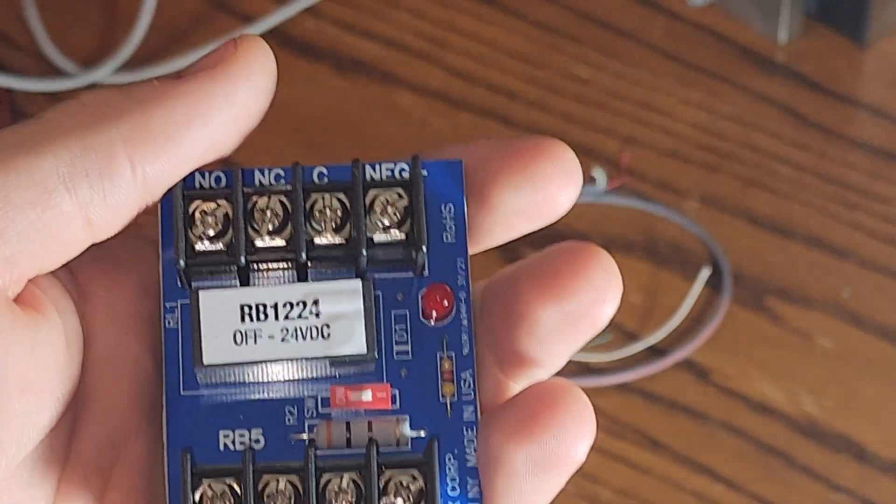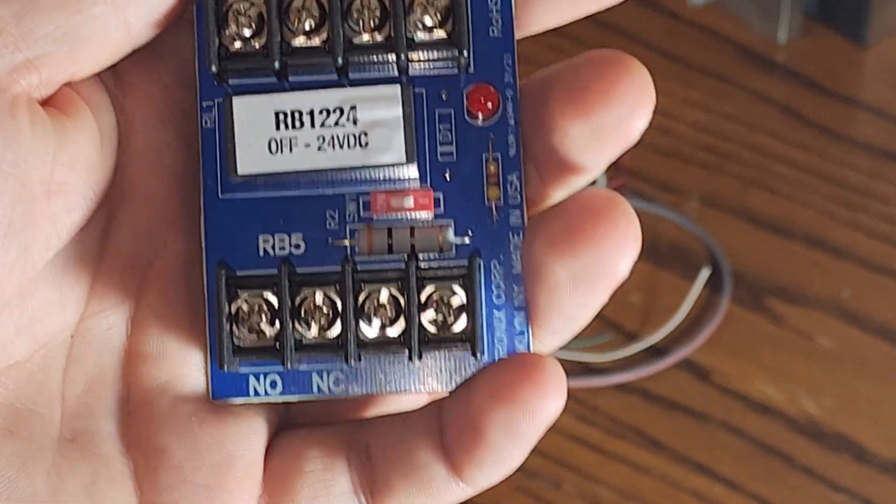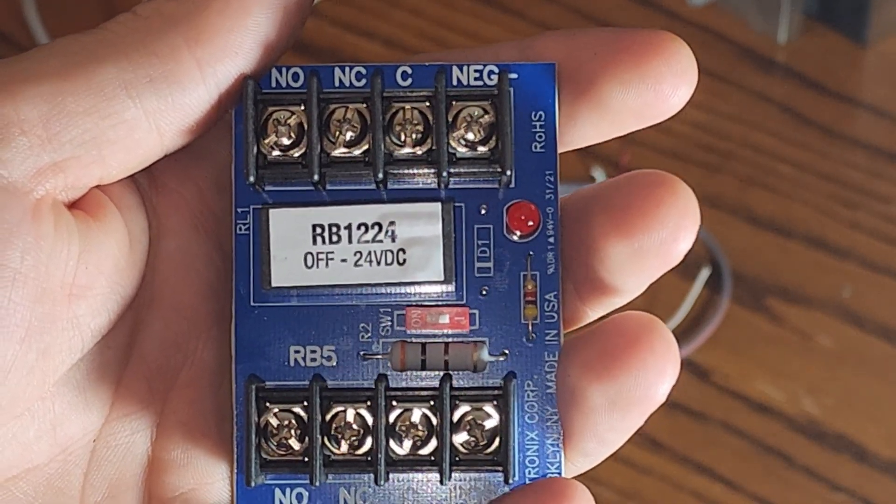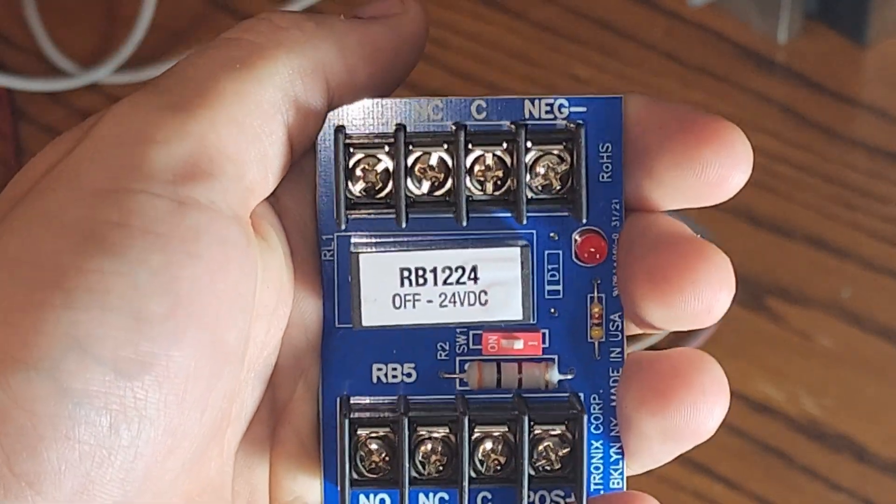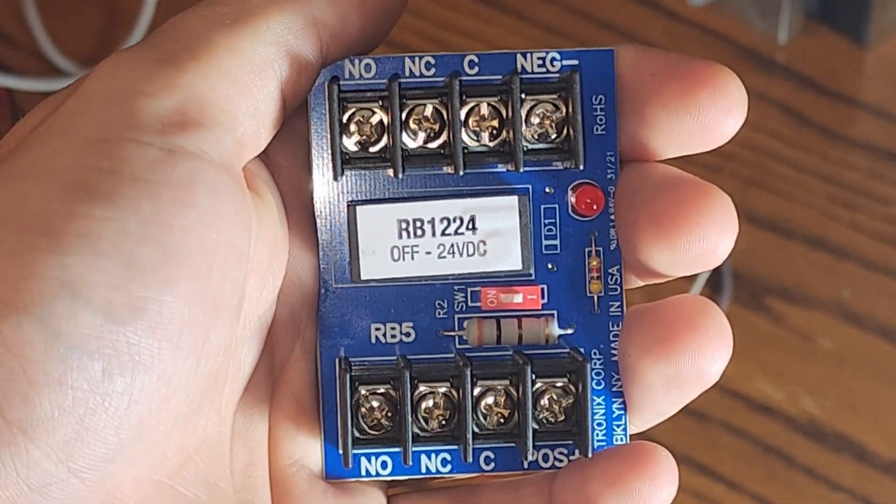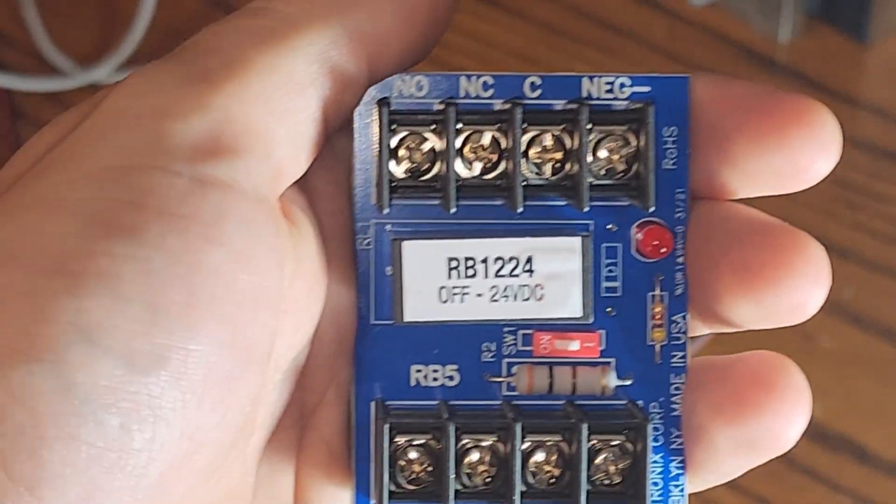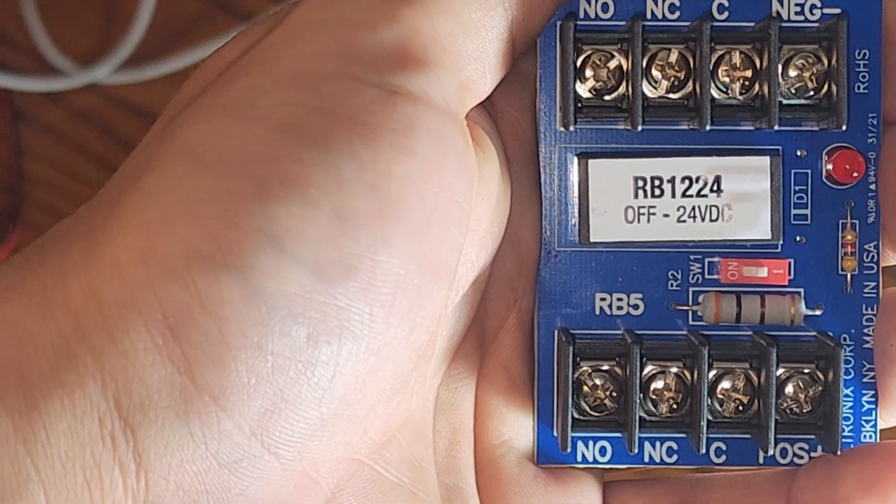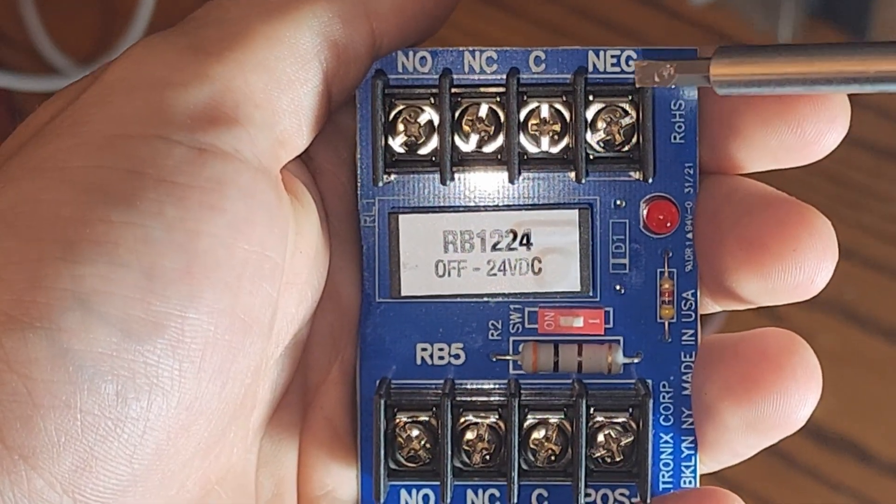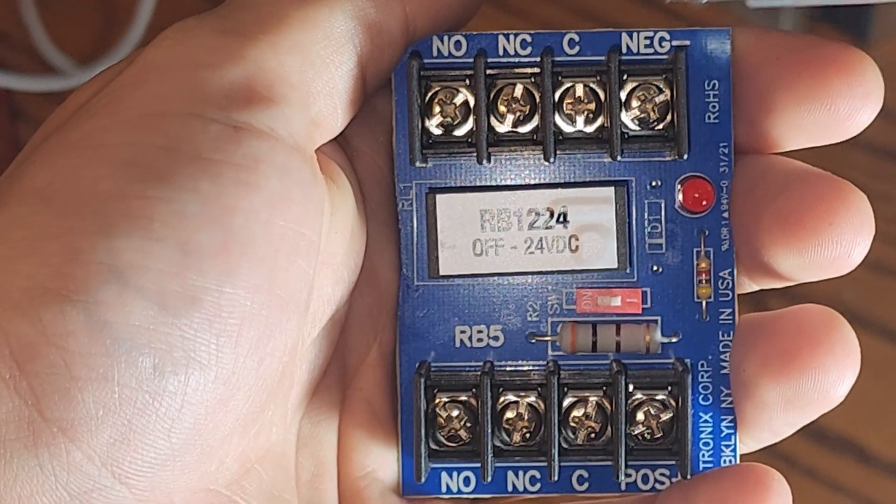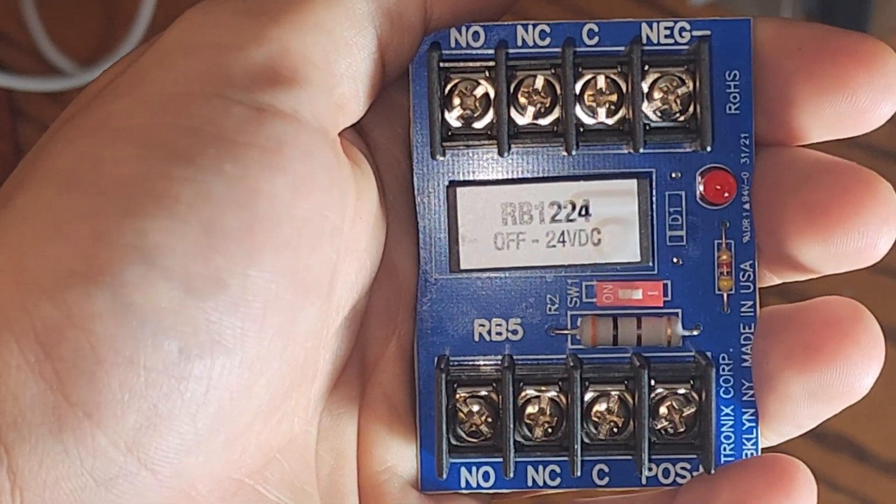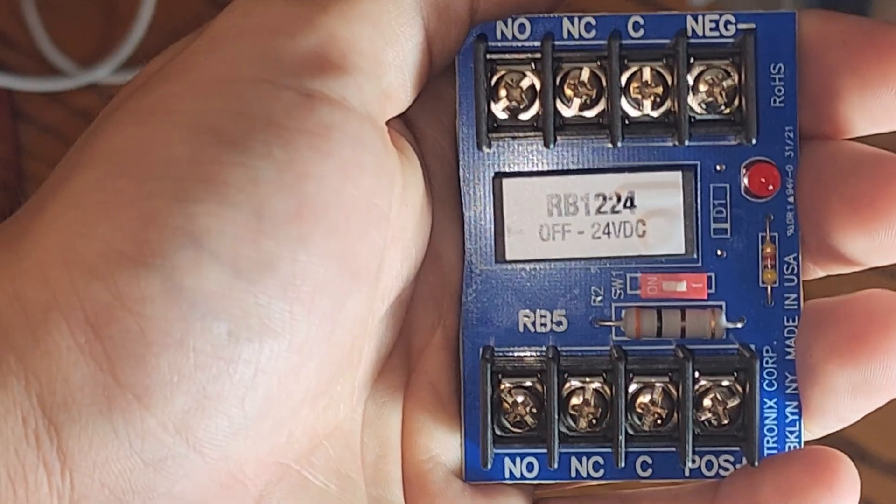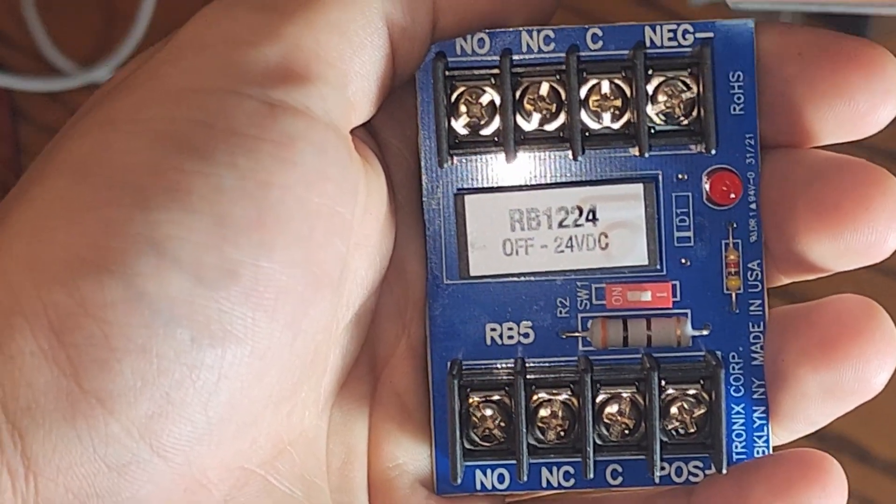So, let's say I wanted to power a lock, and let's say I wanted to do it when there was a HUGS event. HUGS is a very common system we install. It's infant security. It keeps babies from getting stolen. So, let's say that when a baby is near a door, I want the door to lock. Coming off of the HUGS controller, and we will go into better detail on this in the HUGS videos, I would have my positive tied to the positive of that HUGS controller, and then through the relays, I would have a negative trip coming into my negative.